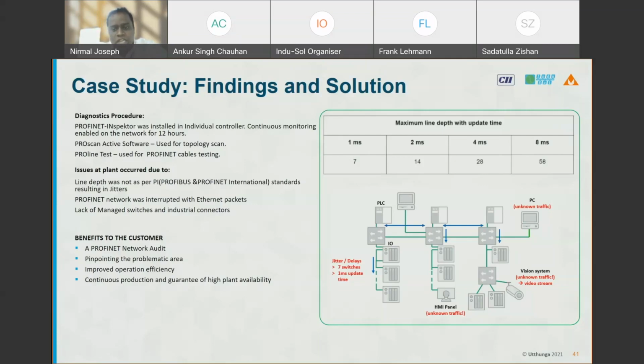Just to brief on the architecture itself, there were delays or jitters based on line depth - Frank has already spoken about this. Just to reiterate, based on the update rate in your network, you need to ensure your line depth is under control, and any devices or infrastructural components that add to your network load need to be checked and considered even before you introduce them into your PROFINET network.